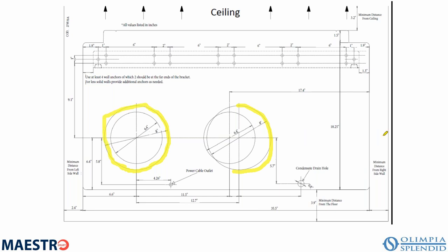However, let's say you have a geometric constraint, a physical impediment that doesn't allow for the 8-inch duct. So you can choose alternately to run two 6.4-inch ducts, okay? Now the recommendation is you do that only when you absolutely have to, because when you have a smaller area through which the air can go in and go out, you suffer some capacity and some efficiency loss. It's not crazy, but it's measurable. And so you only use the smaller holes when absolutely necessary. And here you see the area for the 3/4-inch drain line.